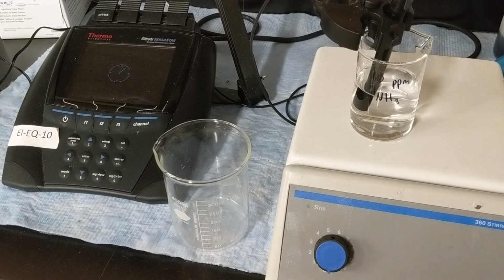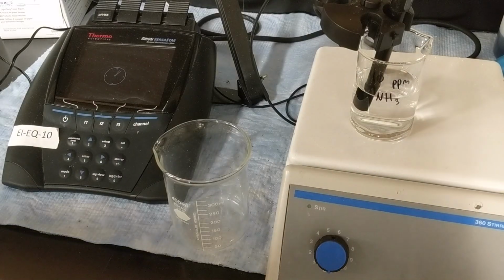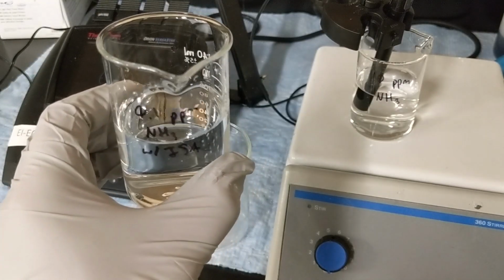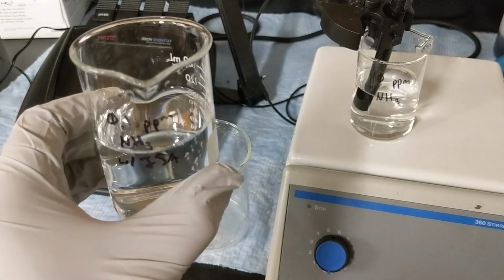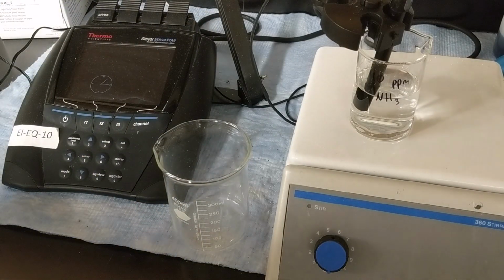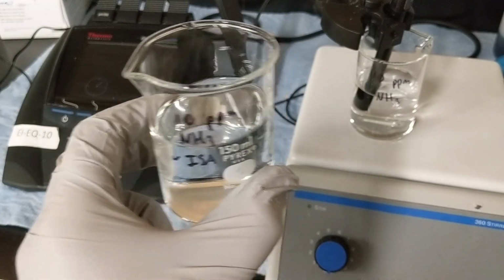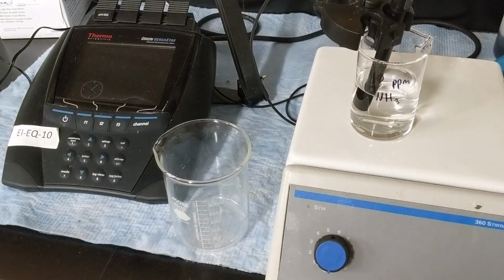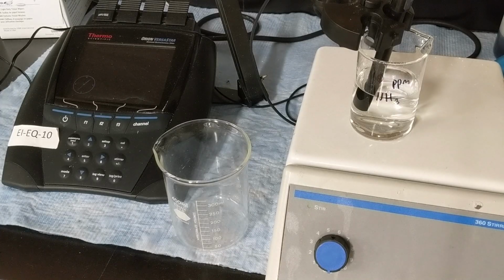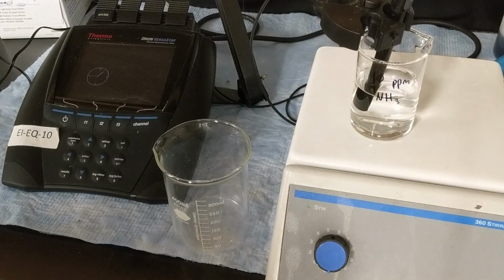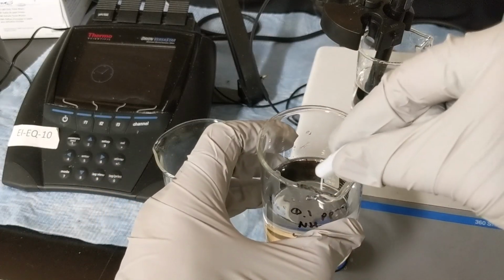So now it is time for us to do our calibration. What I have, again, made off camera is a 0.1 part per million solution of ammonia and another different 10 part per million solution of ammonia. Again, those are both 100 milliliters, and it's important that your calibration standards and also your samples that you're measuring come in at around 100 milliliters to make sure it's consistent. I will also need a couple of magnetic stir bars, so I'm grabbing those from the drawer underneath the pH meter right now. And just going to plop those in.